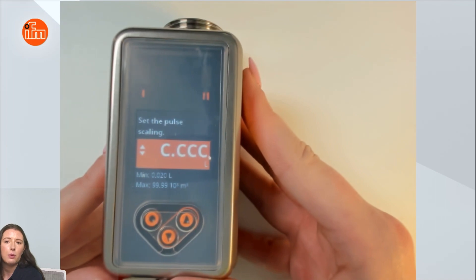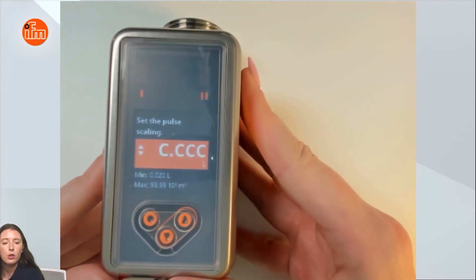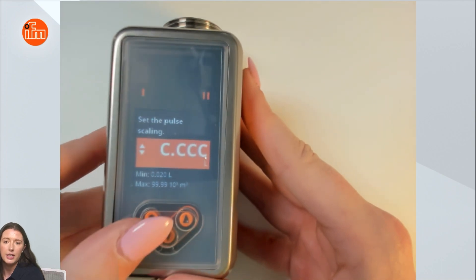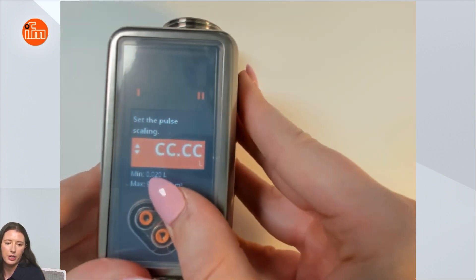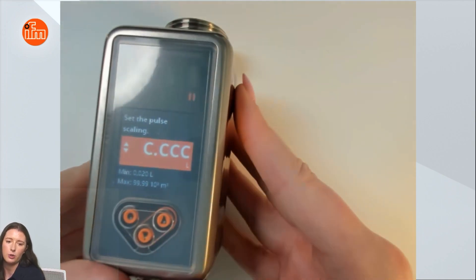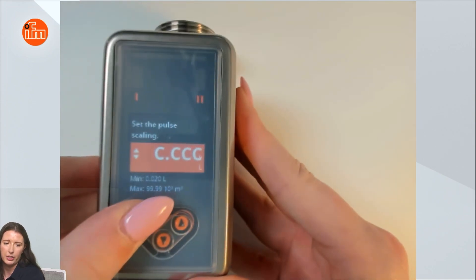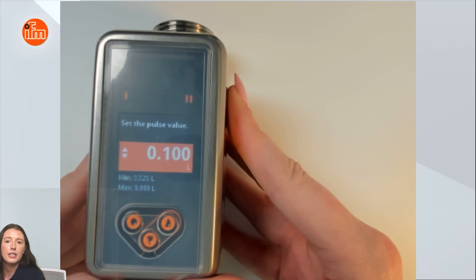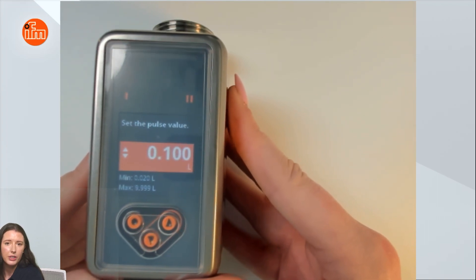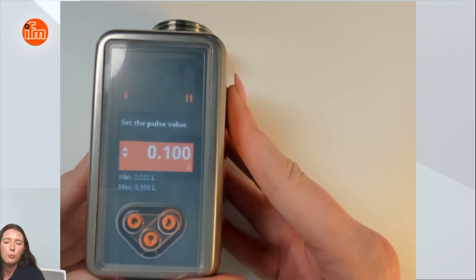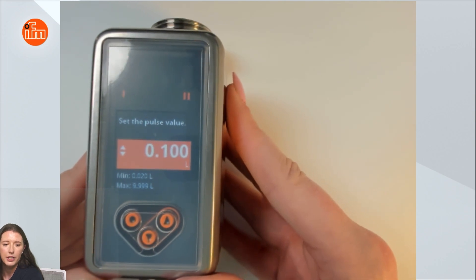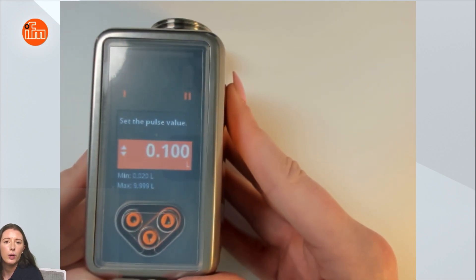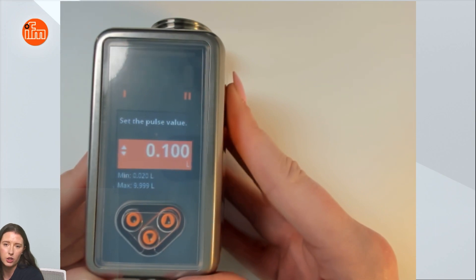Now it's going to ask me what I want my decimal point to be for my totalizer set point. I'm just going to keep it at c.ccc, but if you press up or down you can see that decimal point change. Press enter when you're at what you want it to be, and next you can set the IMPS value. This value is at which point you're going to get a pulsed output. So if I set it for 0.1 liters, every time 0.1 liters passes through the device you will get a pulse.